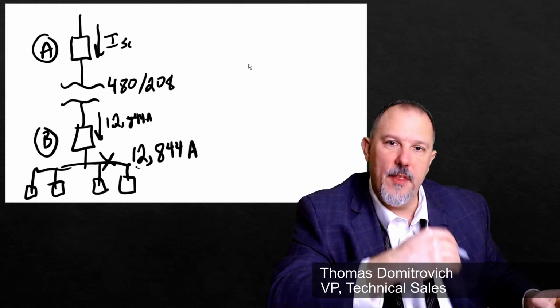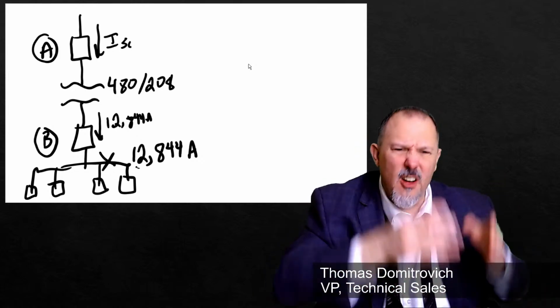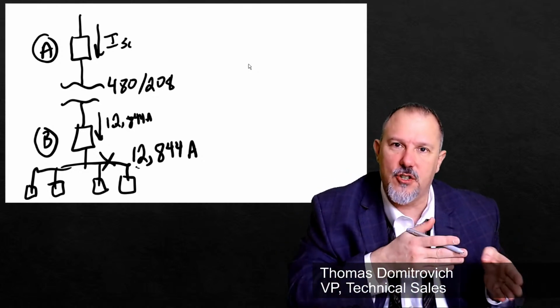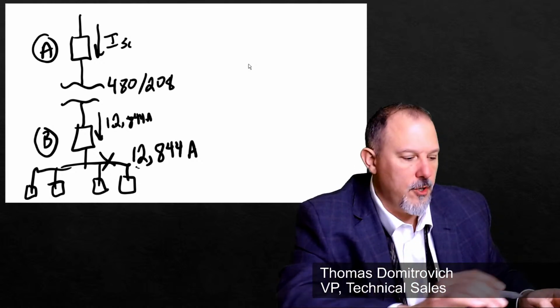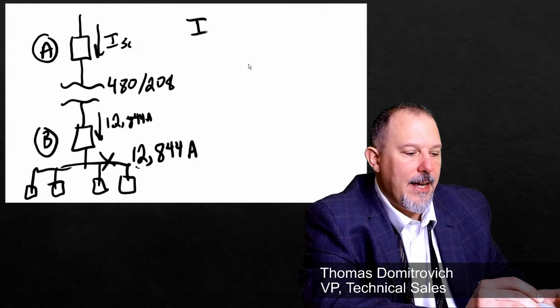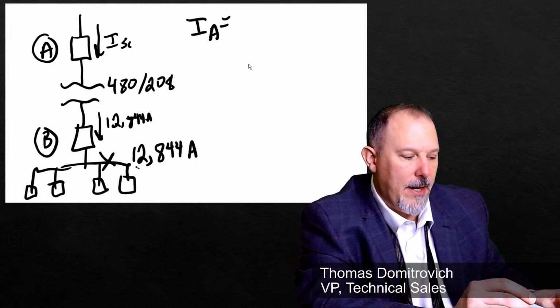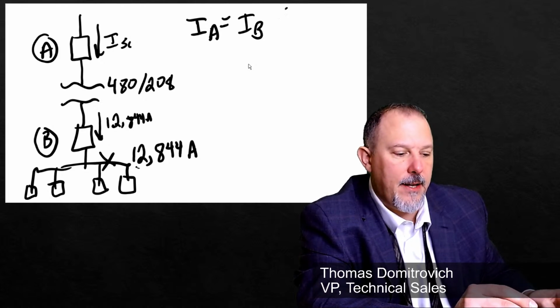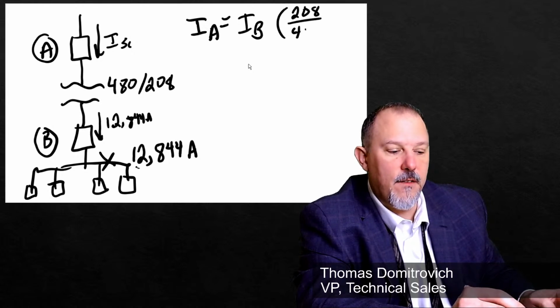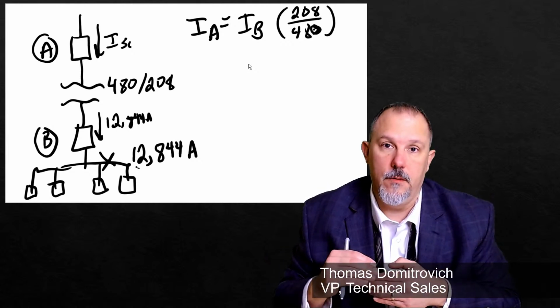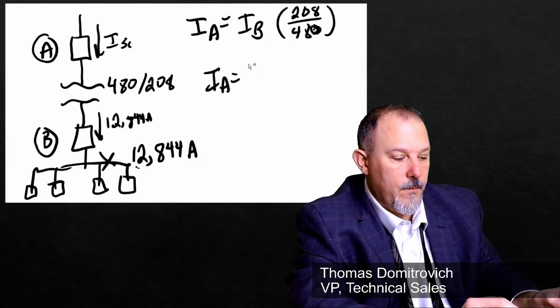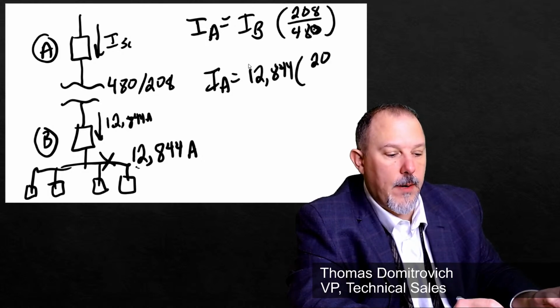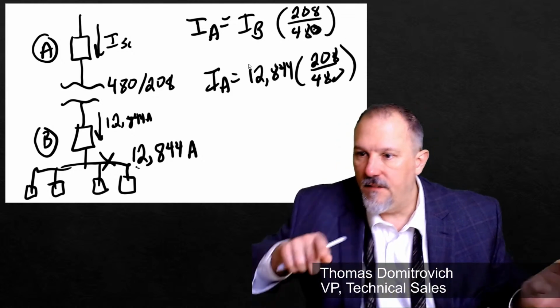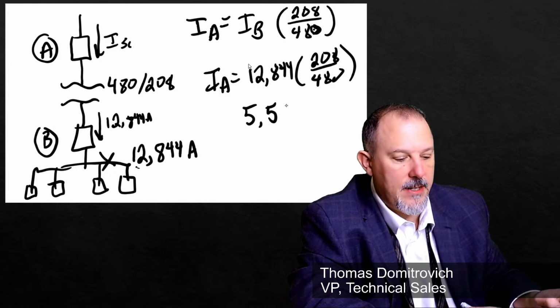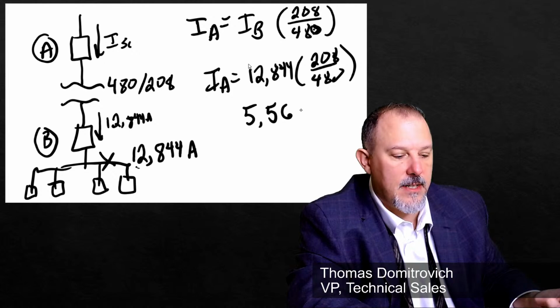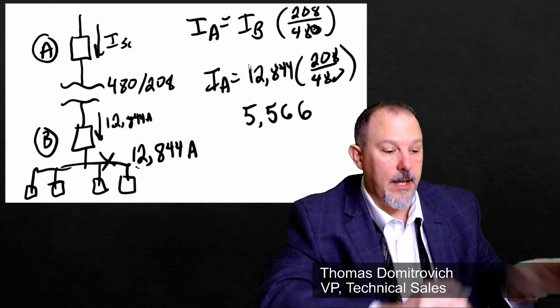How do we know? The transformer does not cease to do its job. The laws of physics do not cease to exist because of a fault current on the secondary of this transformer. The transformer will continue to do its job. What does a transformer do with the turns ratio? IA, which is the fault current flowing through the primary breaker, is going to be equal to IB, the secondary, times 208 divided by 480. The turns ratio. So IA is going to equal 12,844 times 208 divided by 480, which is 5,566 amps. I'm going to trust you on that. Okay, so that's the turns ratio.